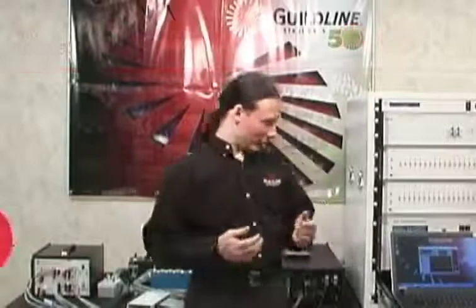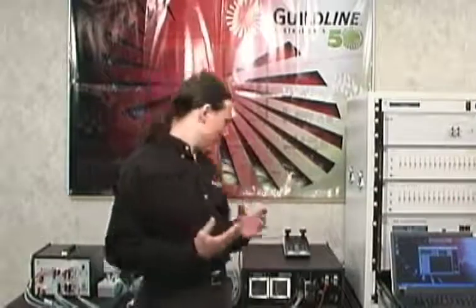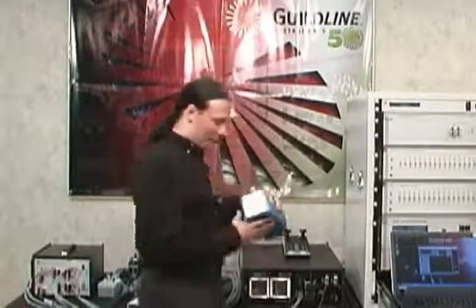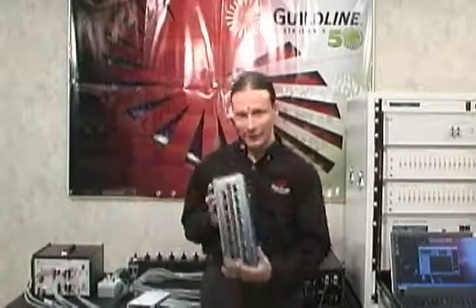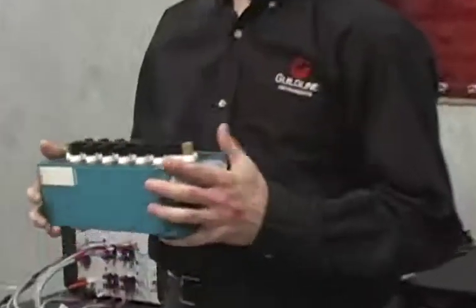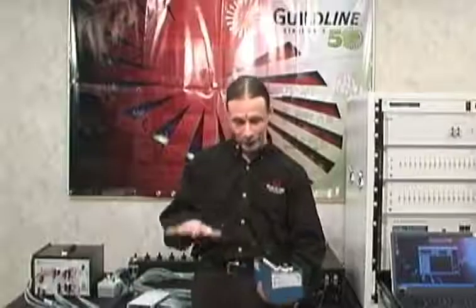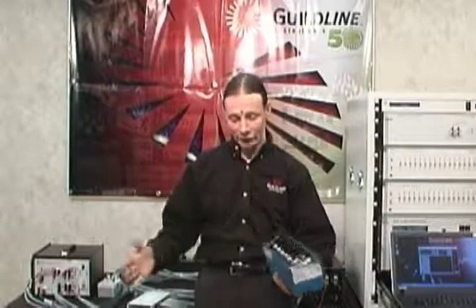We're going to discuss the transfer standard utility this time. Transfer standard utility will be used quite extensively throughout the militaries. This is a transfer standard here. This is an SR1010 box. They also make a 1030 with 3 of them in an oil bath, and a 1060 which has 6 of them in an oil bath.